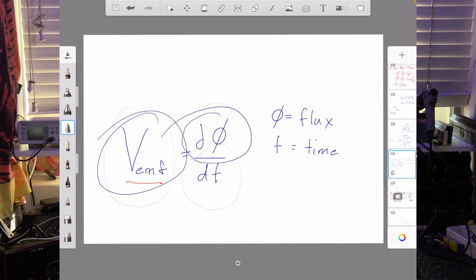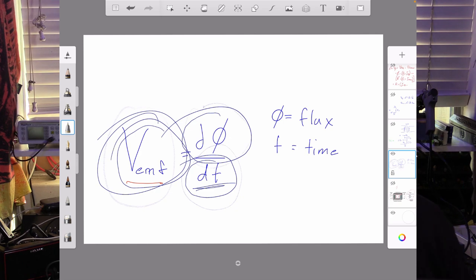As you can see, if the time taken in the change of magnetic flux can be extended, made larger, that will reduce the induced voltage and the inrush current. So we could use an NTC, a negative temperature coefficient thermistor, and by increasing that time to charge, it will reduce that voltage and in turn the current.